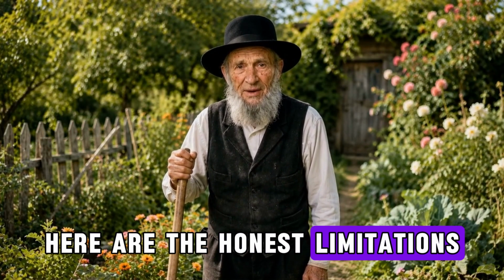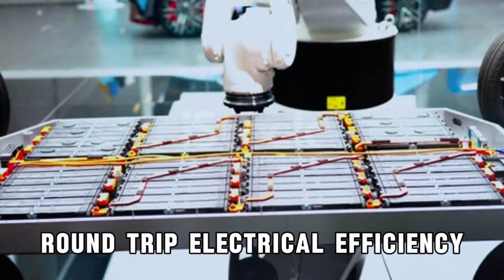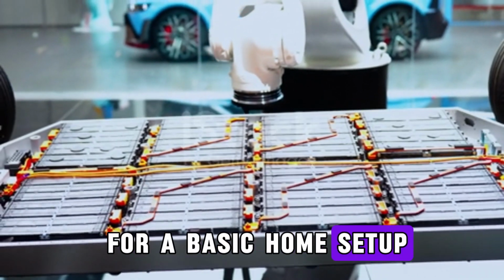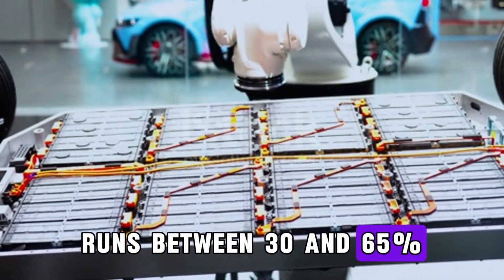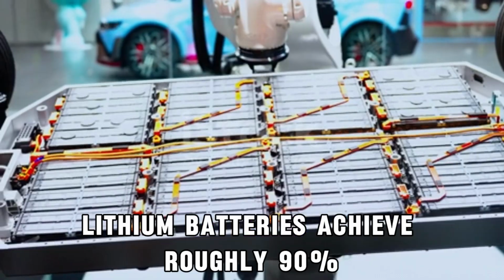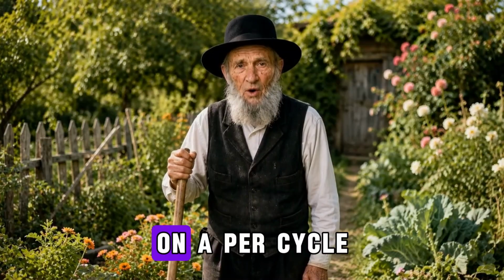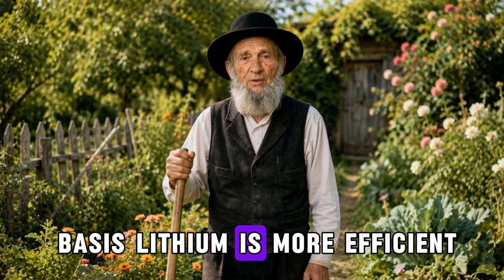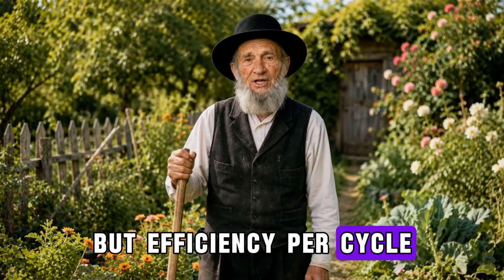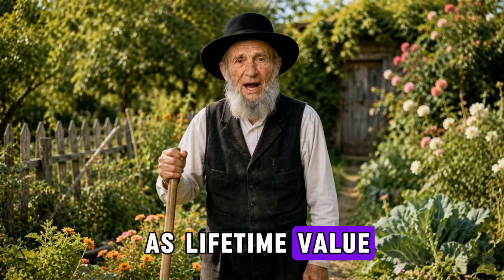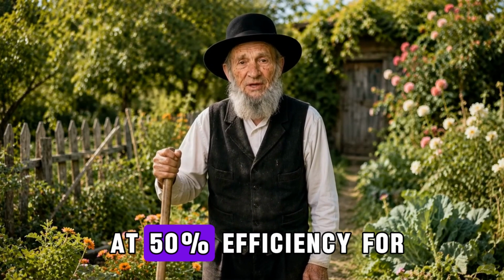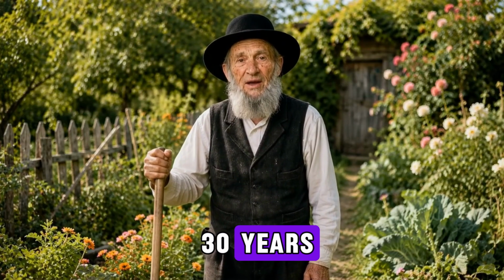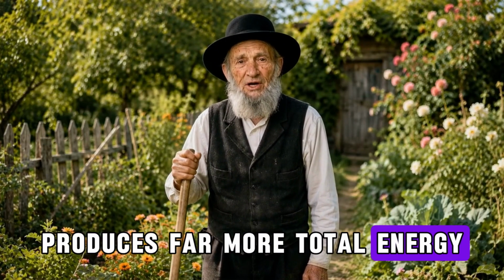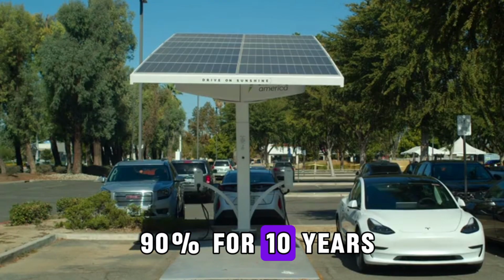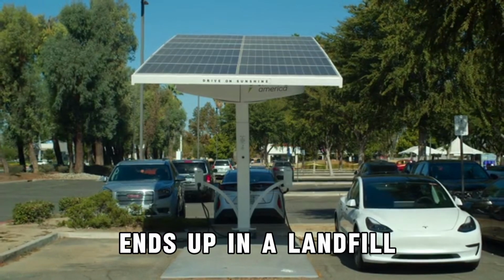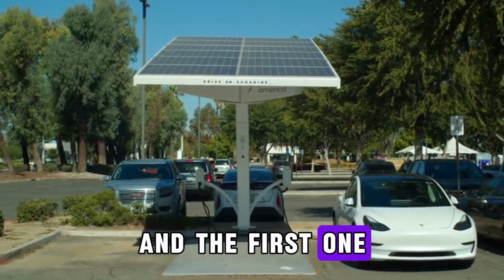Here are the honest limitations. Round-trip electrical efficiency for a basic home setup runs between 30 and 65%. Lithium batteries achieve roughly 90%. On a per-cycle basis, lithium is more efficient. But efficiency per cycle is not the same as lifetime value. A system that runs at 50% efficiency for 30 years produces far more total energy than one running at 90% for 10 years, because the second system ends up in a landfill and the first one keeps running.